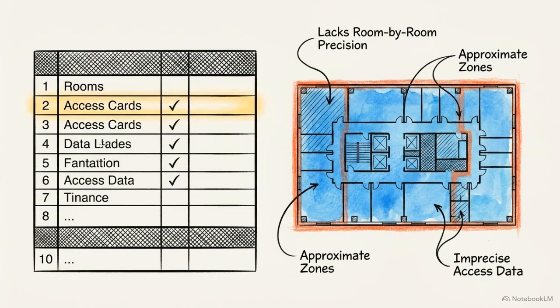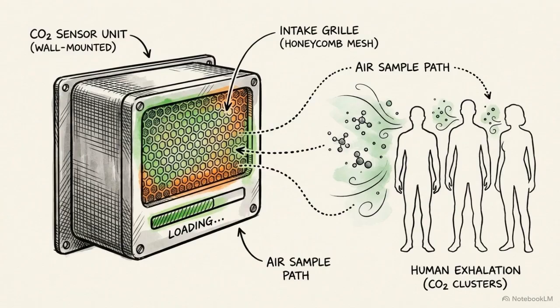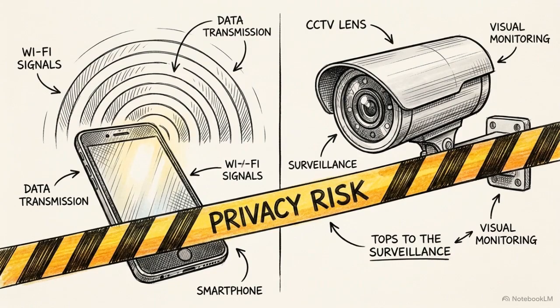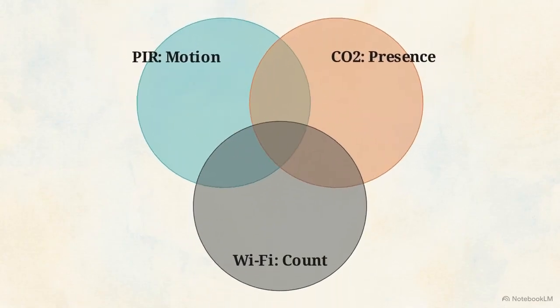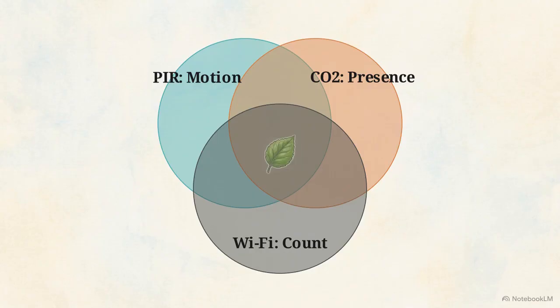PIR motion sensors detect movement, but miss stationary workers. Access card swipes count entry at the door, but only provide broad, floor-level estimates. Carbon dioxide sensors measure human exhalations, which makes them highly accurate for scaling crowds, but they have a delayed response time of several minutes. Then we have device-level Wi-Fi tracking and camera-based human shape counting. While technologically advanced, both face severe privacy and regulatory roadblocks. Because no single sensor is flawless, intelligent infrastructure design relies on layering multiple, overlapping detection methods to paint an accurate picture of human activity.